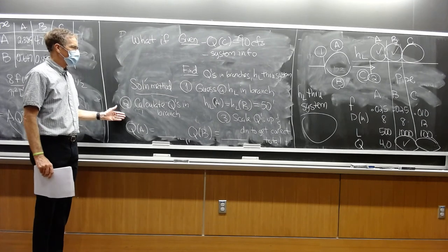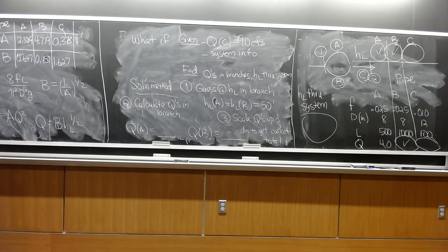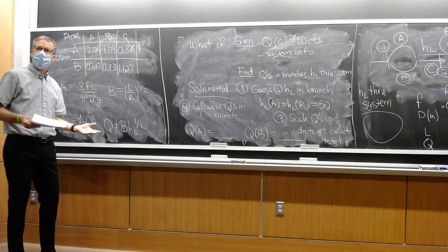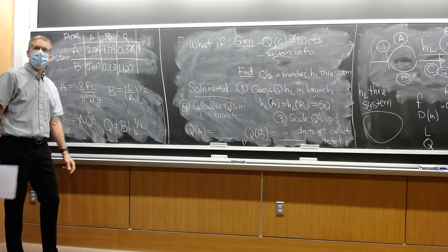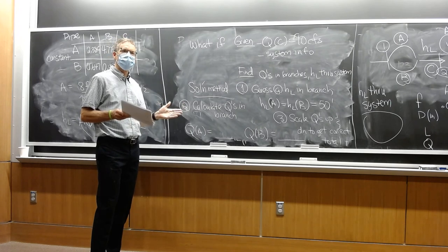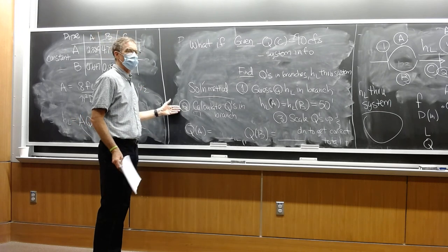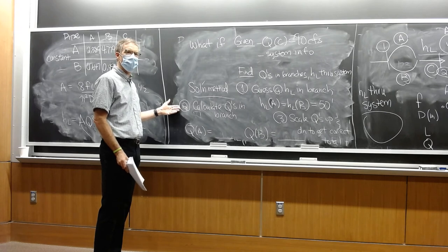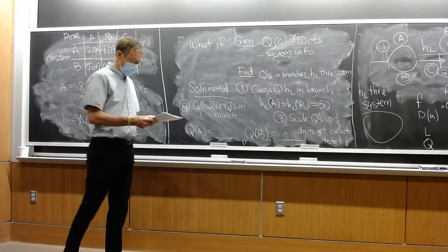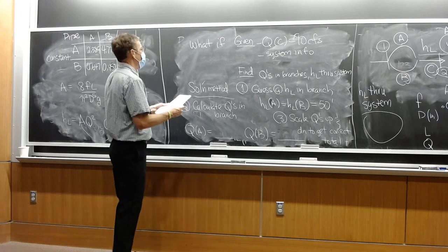And the nice thing is that split, as you vary the head loss by a particular amount, the Q's are going to go up and down by a factor that has to do with how much you change the head loss. And so once you calculate the distribution of flows for an assumed head loss, that distribution of flows will stay the same regardless of what the head loss is. And that justifies doing what we're doing here to scale the flows up and down. And then once you've done that, scale Q's up and down to get the correct total. I'm just going to put it over here.